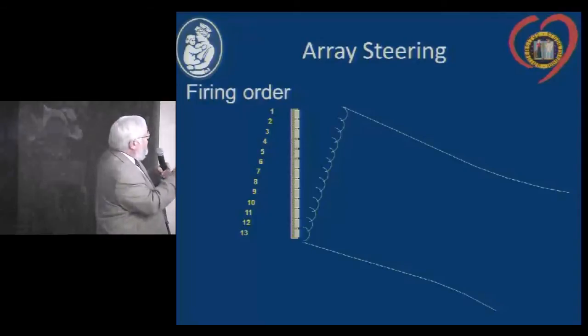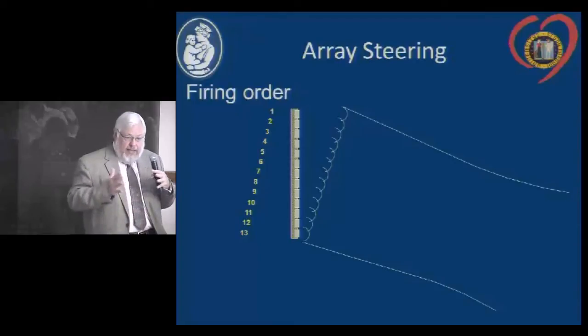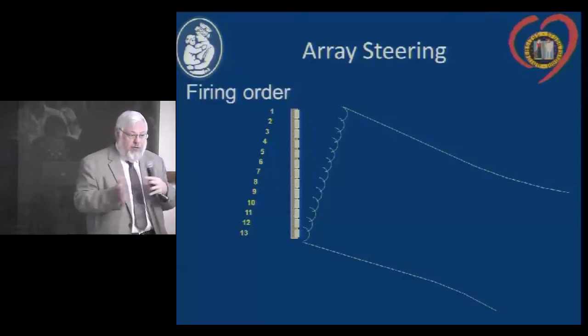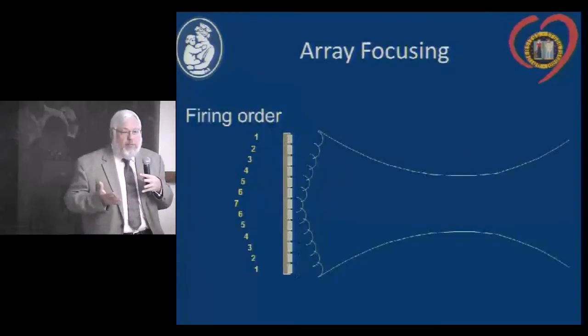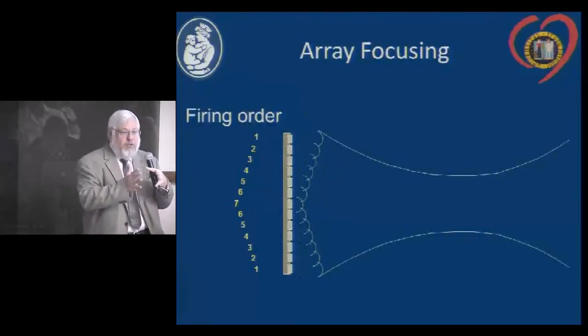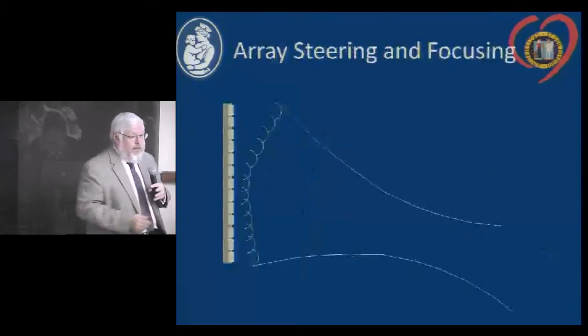Each element creates its own wavelet. The wavelets coalesce through constructive and destructive interference to create the beam emanating from the array transducer. By changing or phasing the excitation of each crystal — so-called phased array transducers — you steer the beam. By changing the timing of firing each transducer element, based on wave interaction physics, the beam is steered back and forth. In an even more complex fashion, you can also accomplish focusing the beam as well as steering it.